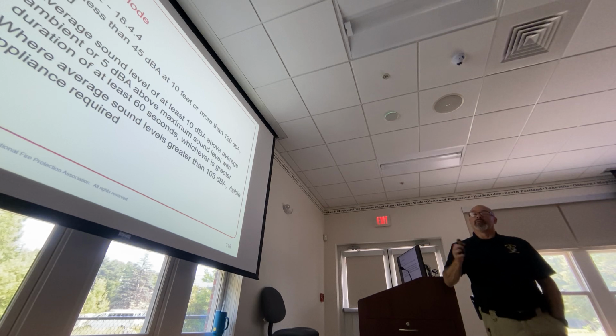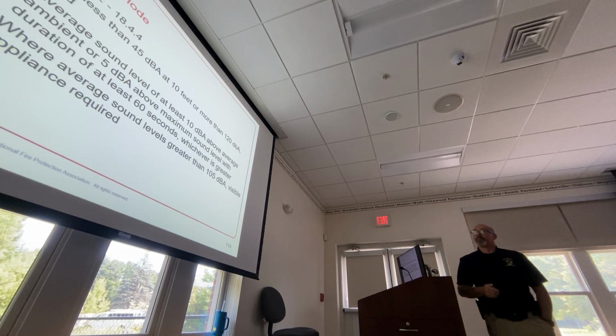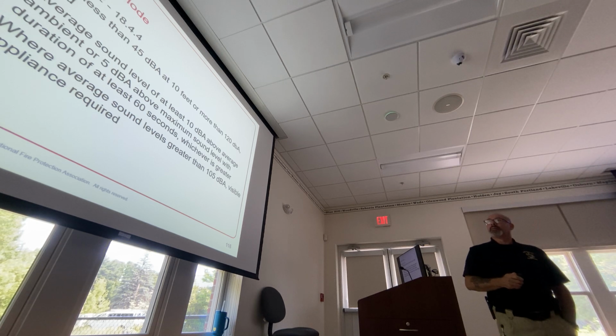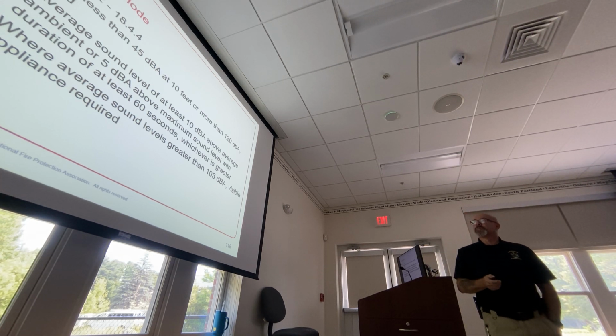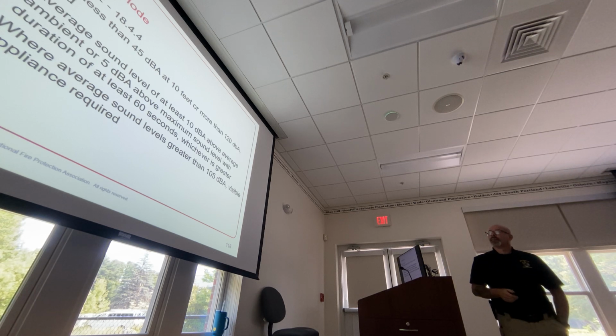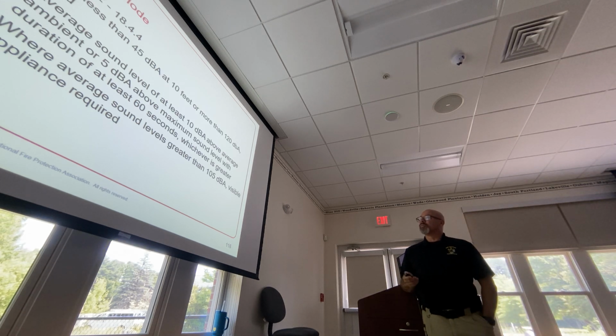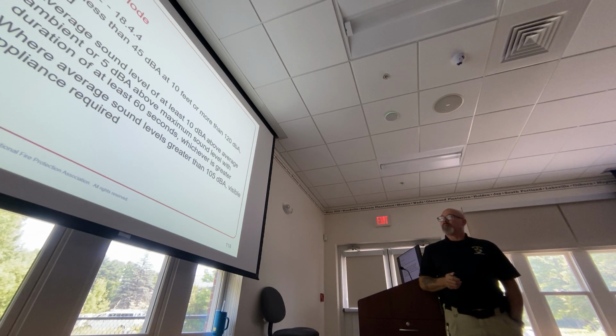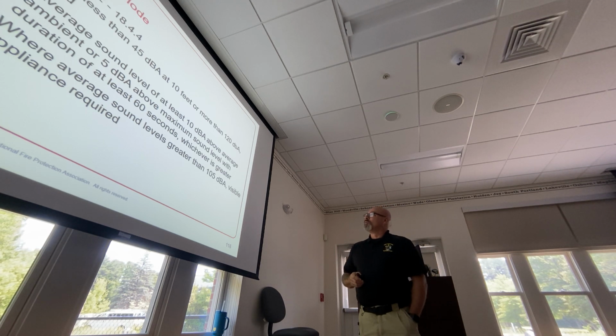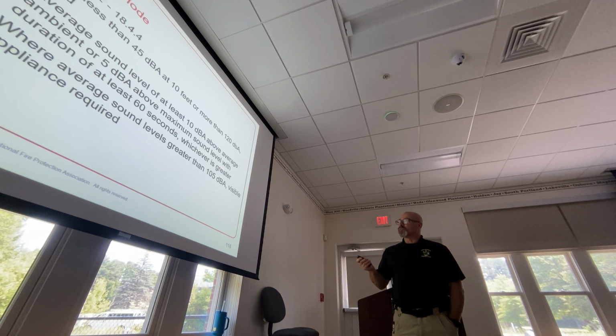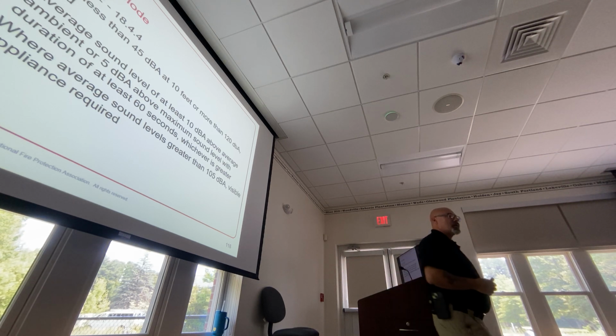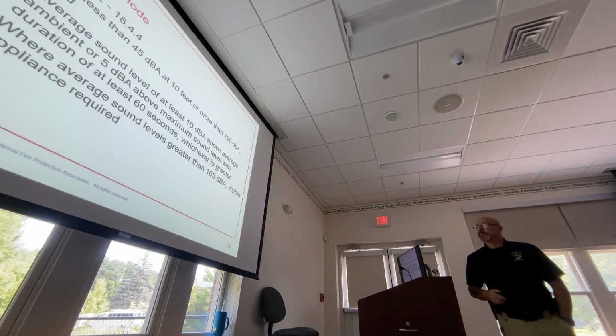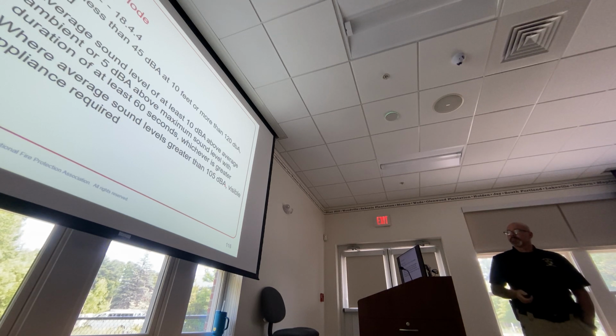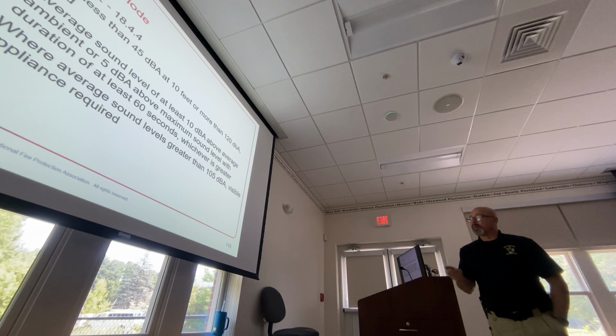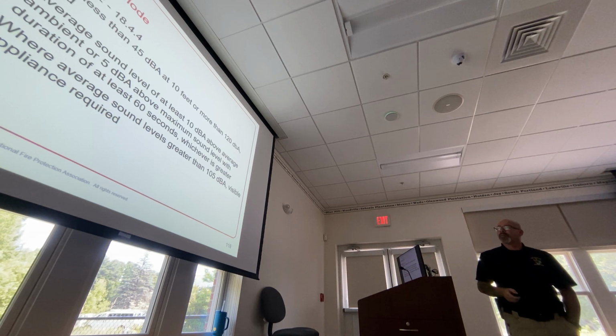We take it a little further with the private mode. If the fire alarm does have to go off and activate, it has to be not less than 45 decibels at 10 feet or more than 120 decibels, and average sound level at least 10 decibels above the average ambient or 5 above maximum sound level with duration of at least 60 seconds, whichever is greater. A little bit confusing on how that reads, okay? Same scenario, 105 decibels: a visible appliance is required if it's louder than 105 decibels.